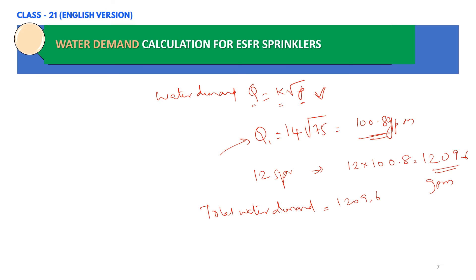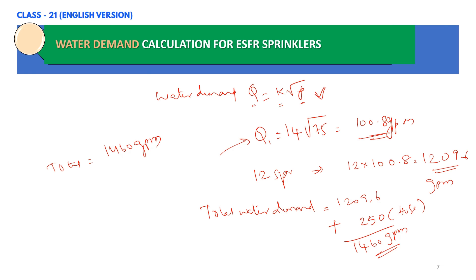To select the fire pump, we need to add the hose stream allowance of 250 GPM to the sprinkler demand of 1209.6 GPM, giving a total water demand of approximately 1460 GPM. The duration is 60 minutes, so the water tank capacity = 1460 × 60 = 87,600 gallons.